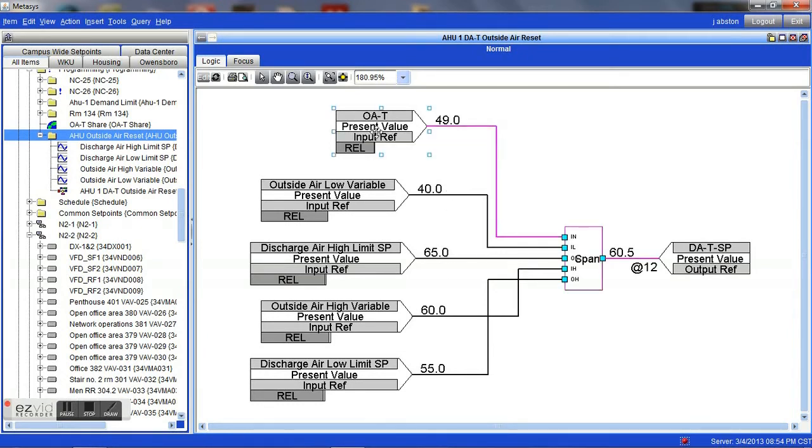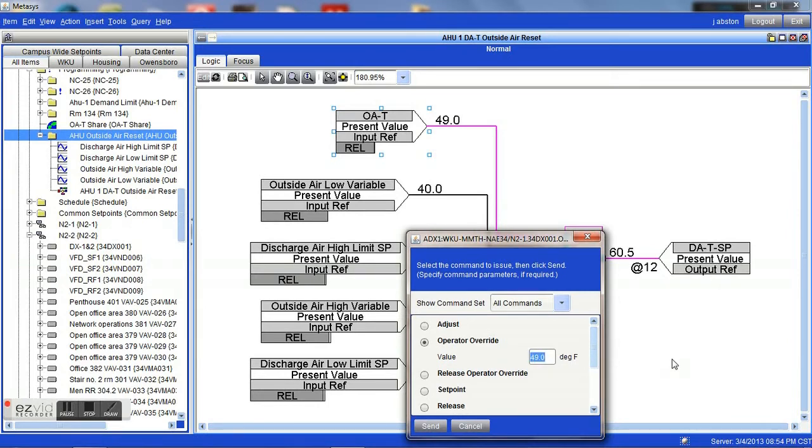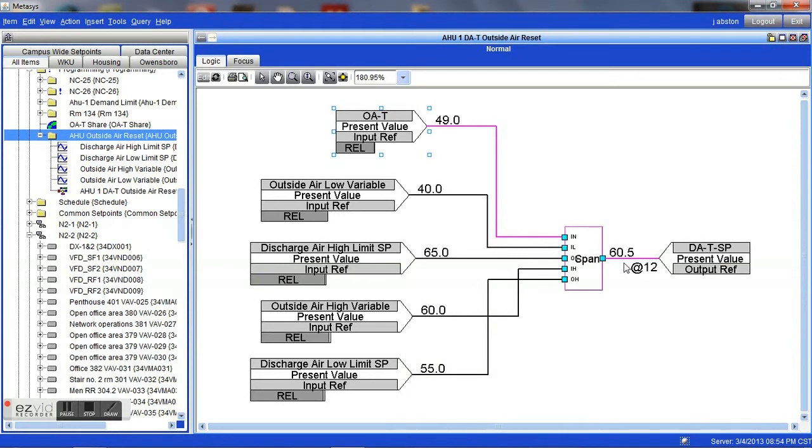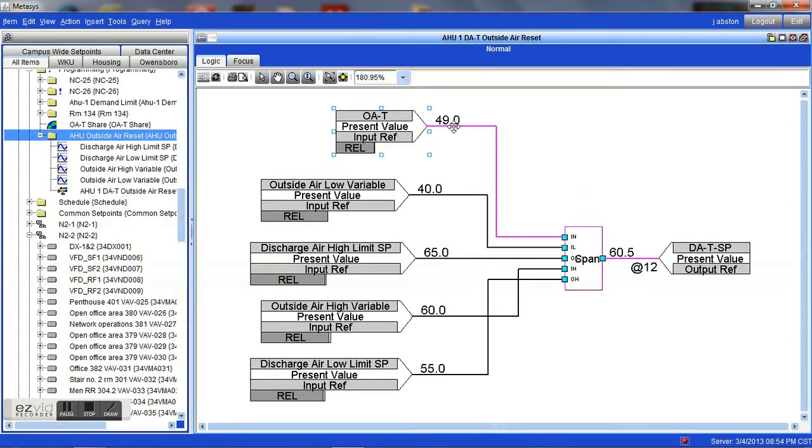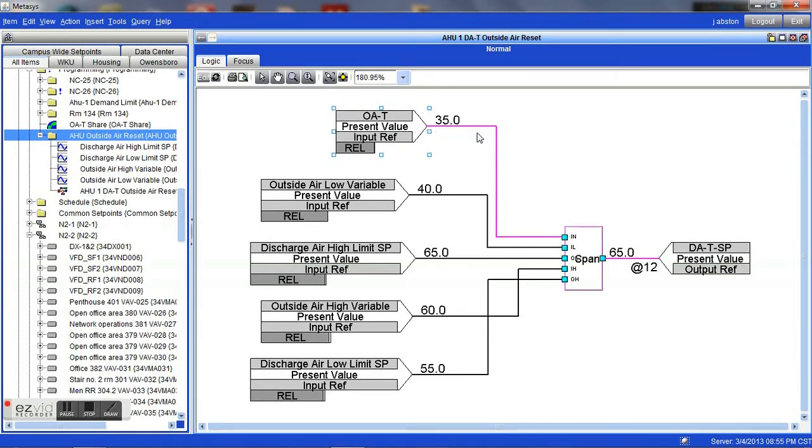For example, if it will allow me, I will demonstrate. All right, if I were to change my outside air temperature, say if we went colder outside for whatever reason, let's say that we got down to 35 degrees. You will notice that this air handler based upon that temperature value will readjust our discharge temperature set point. There, as you can see, now we're showing an outside air temperature of 35 degrees, which is not actually 35, it's just I overrode the logic, and it has calculated up to our maximum output set point.